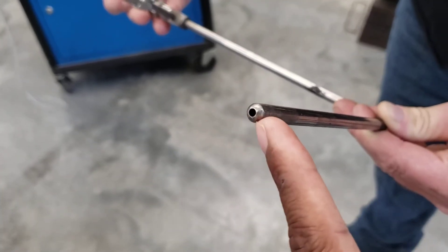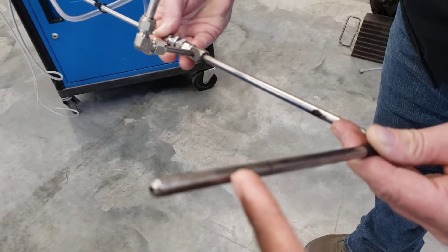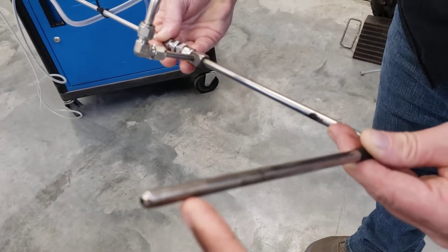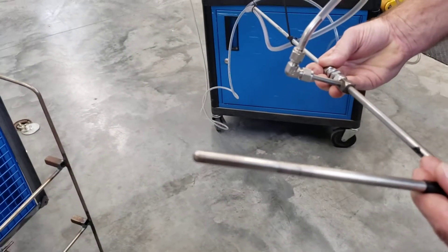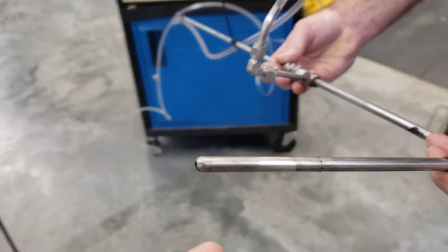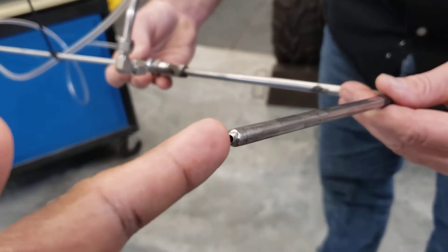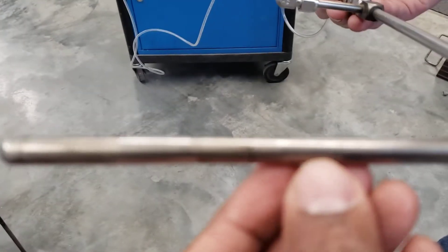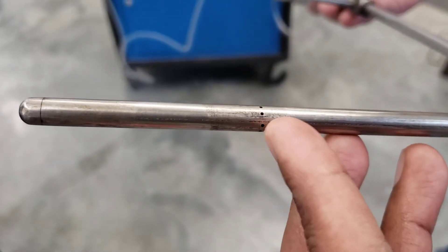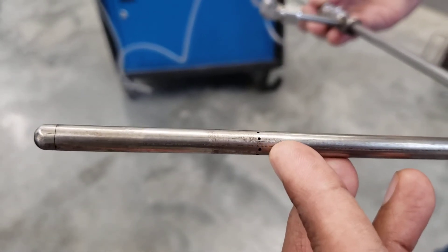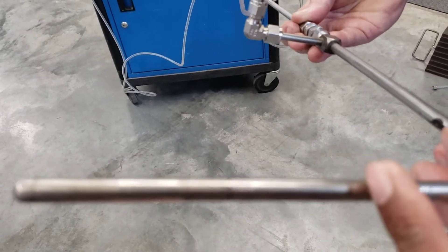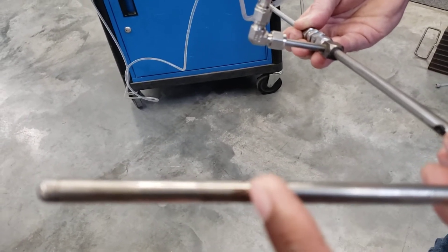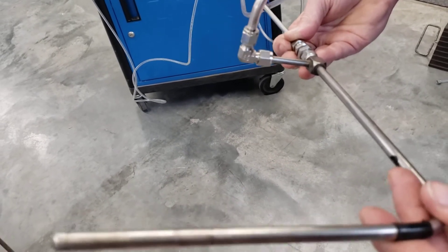There is a hole there and a hollow tube, so it's not a solid piece. When you place this and the flow is coming straight this way entering the tip, it will read both dynamic and static pressure. You can see a bunch of holes here on the outside tube which will only read static, because when it's going this way there will be only static pressure on this surface since the surface particles are not moving.